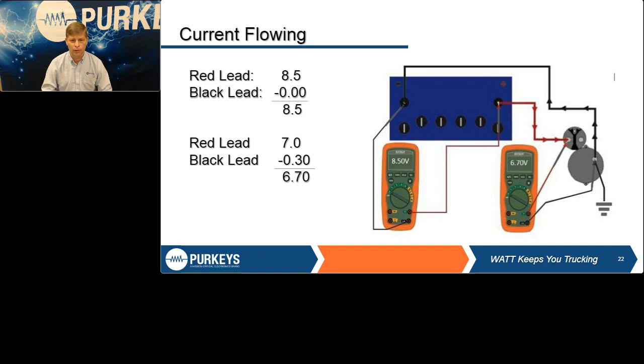I take my second meter going across the starter. What do I read at the red lead? 7 volts. What do I read at the black lead? Negative 0.3. What is the difference there? 6.7. So how much voltage drop do I have in this entire circuit? If you subtract the 6.7 from 8.5, that tells you there is a 1.8 volt drop in this entire circuit.